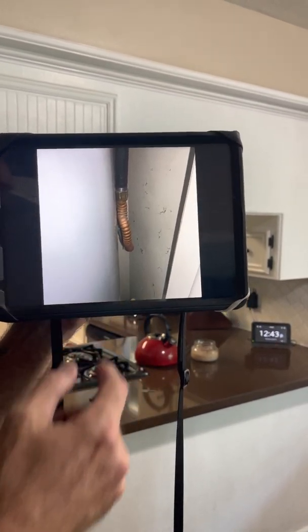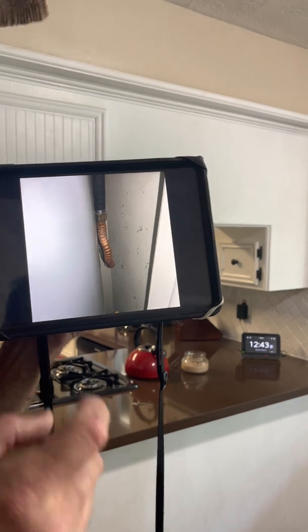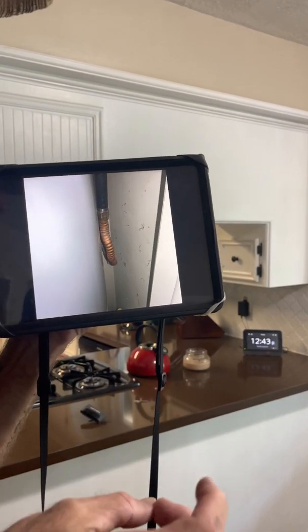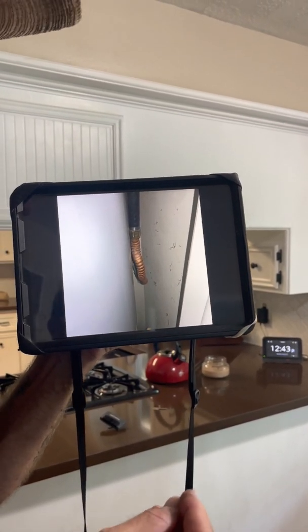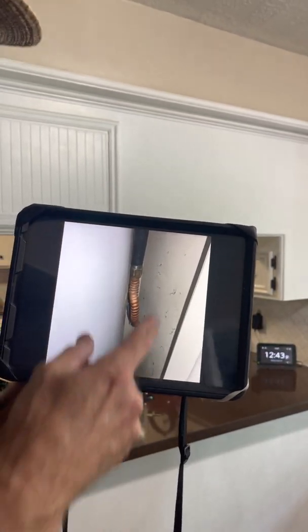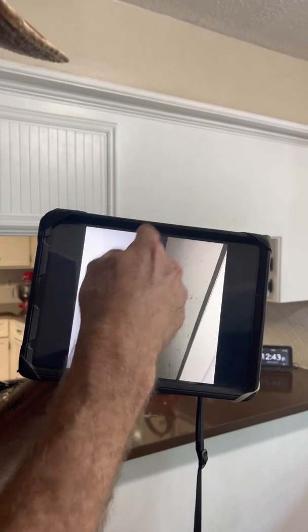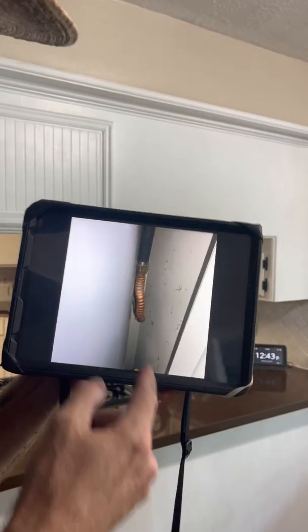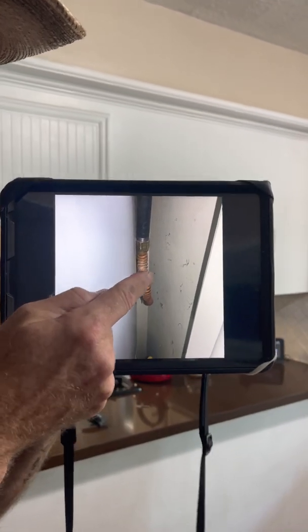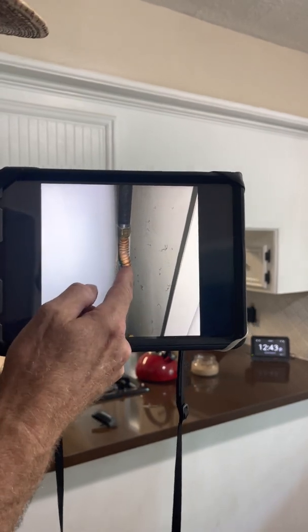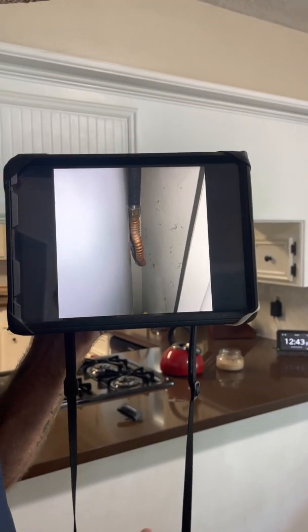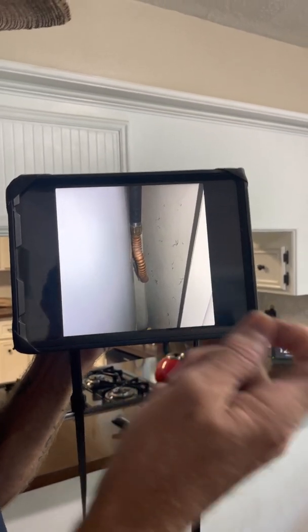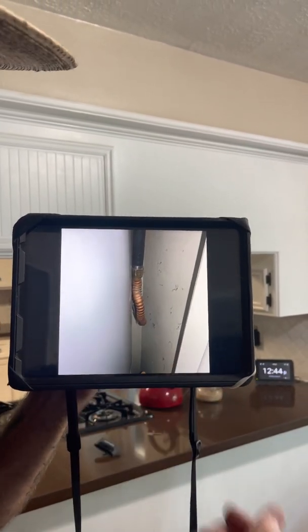A TPR safety valve. Yes. Explain again what that is. TPR is an acronym for temperature and pressure relief valve. So if the temperature gets too high or there's too much pressure, boom, it's supposed to go off, and water's supposed to flow out to relieve the pressure. Water's not going to flow properly through this device because this is wrong. It's a restricted line, restricted by both diameter and by the kinking.